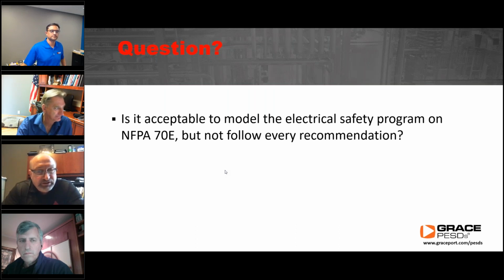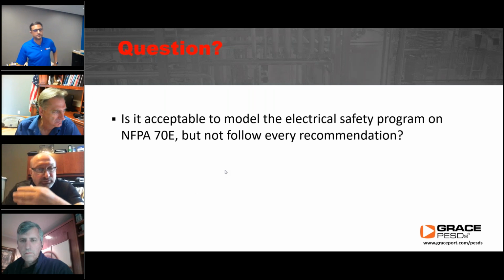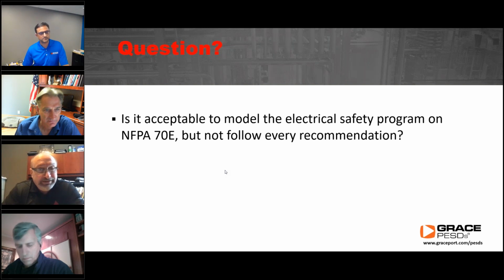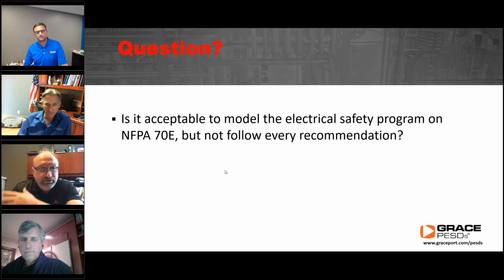So your electrical safety program, and there is specific content in 70E and Z462 advising you that your electrical safety program should have this information in it. So I would say that you need to make sure that that prescriptive content that 70E and Z462 require are in your electrical safety program. We mentioned a few things like the energized electrical work permit, right? So that's a mandatory requirement. Some companies say, well, we're doing what Z462 or 70E tells, but we haven't fully implemented the permit yet, right?